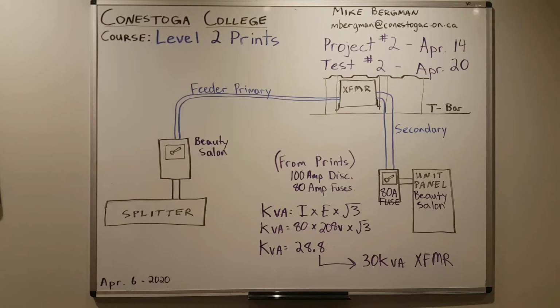All the disconnects you have on, I believe it's drawing E5, those will remain the same for the secondary side of your transformer. We're not changing what these units are getting fed with as far as current is concerned. We're not changing the panels or the disconnects that feed the panels. What we want to calculate now is that feeder. So what we have to do is calculate the size of the transformer so we know what size the feeder, raceway, and conductors are going to be feeding the transformer.